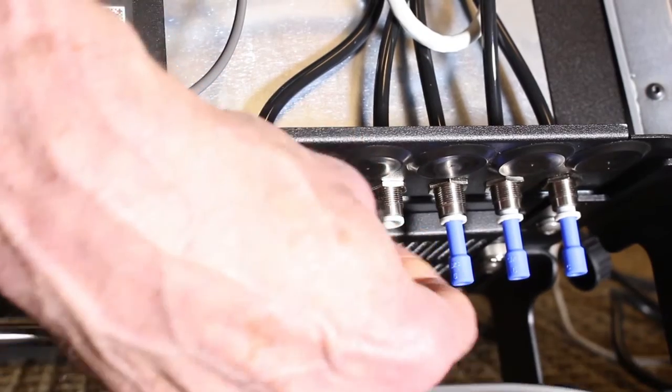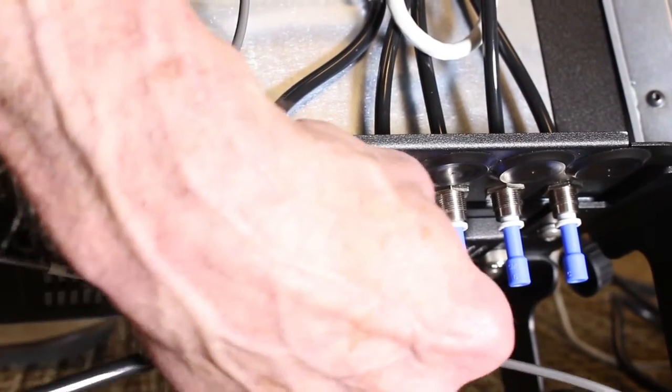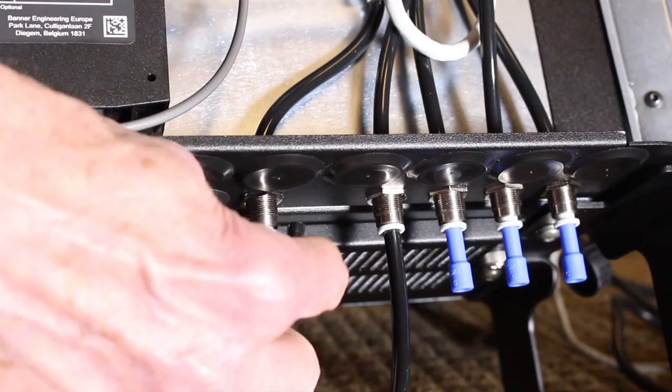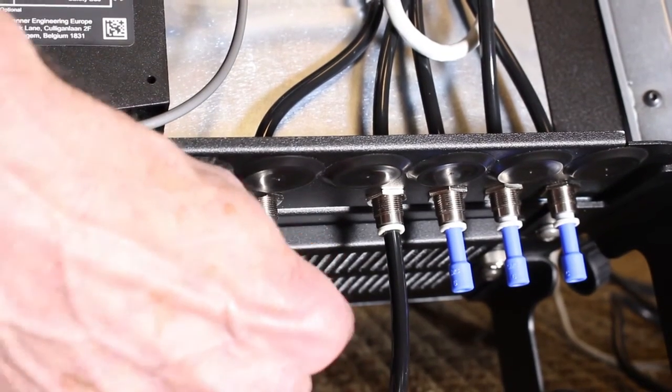Connect the input port to a six millimeter hose with 60 to 90 pounds of dry compressed air. Connect the output side to a hose that connects to the vacuum gripper.